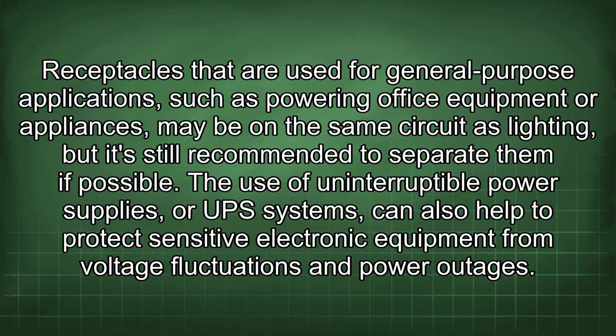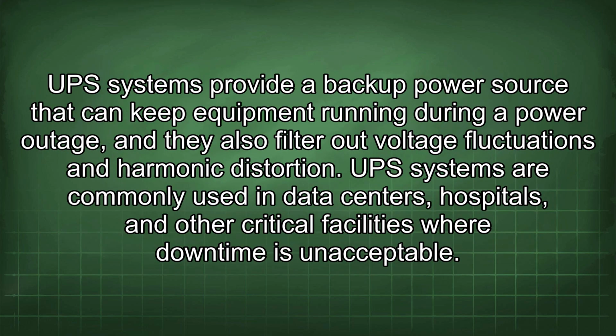The use of uninterruptible power supplies, or UPS systems, can also help to protect sensitive electronic equipment from voltage fluctuations and power outages. UPS systems provide a backup power source that can keep equipment running during a power outage, and they also filter out voltage fluctuations and harmonic distortion. UPS systems are commonly used in data centers, hospitals, and other critical facilities where downtime is unacceptable.